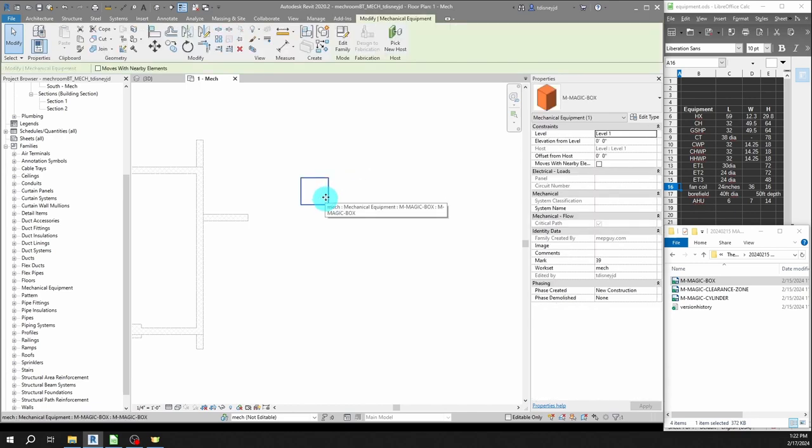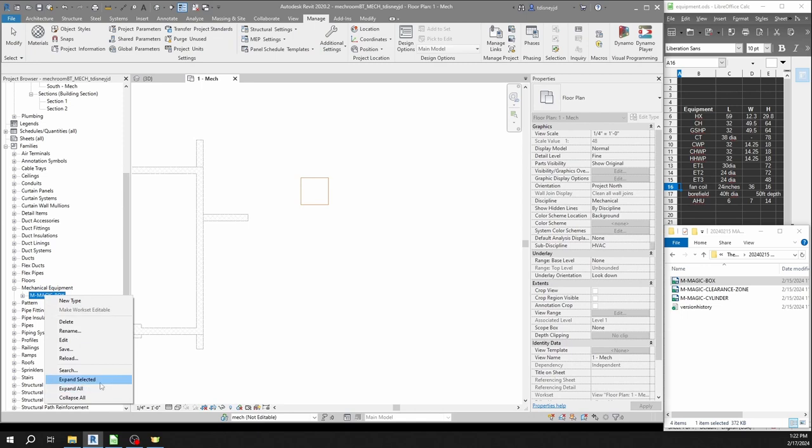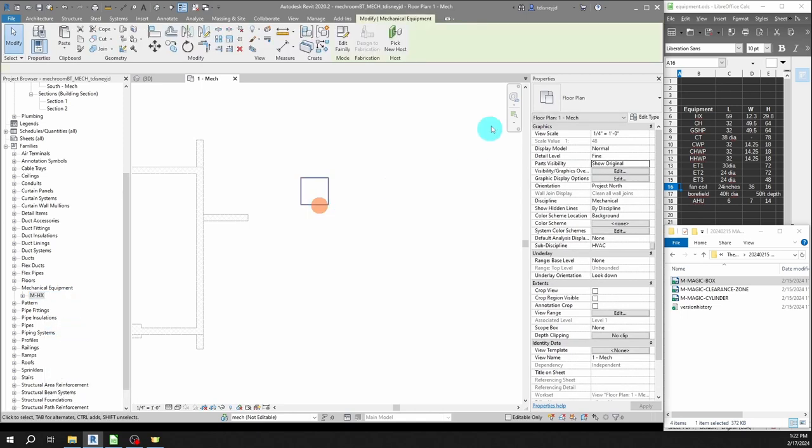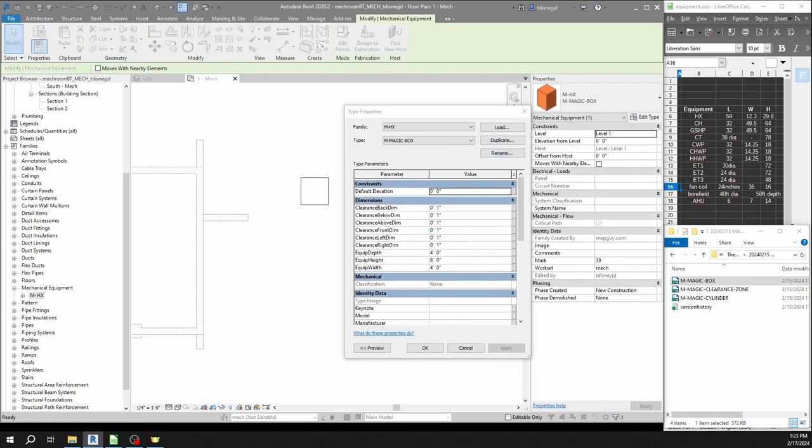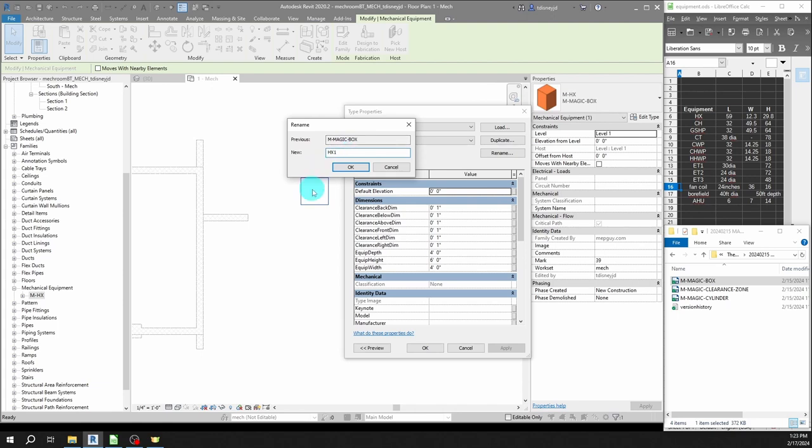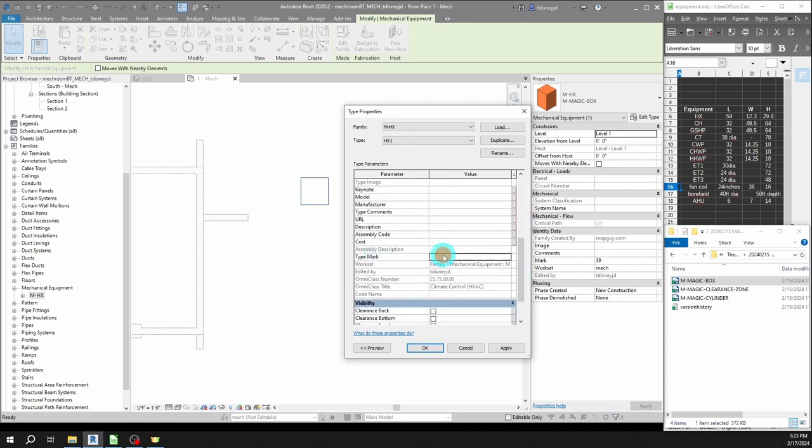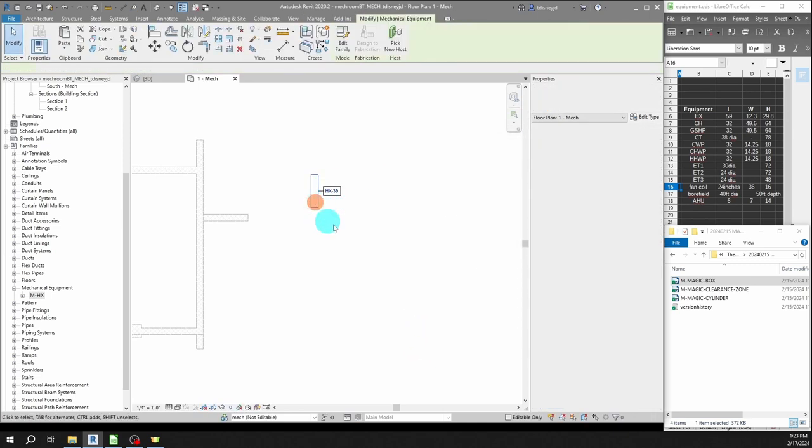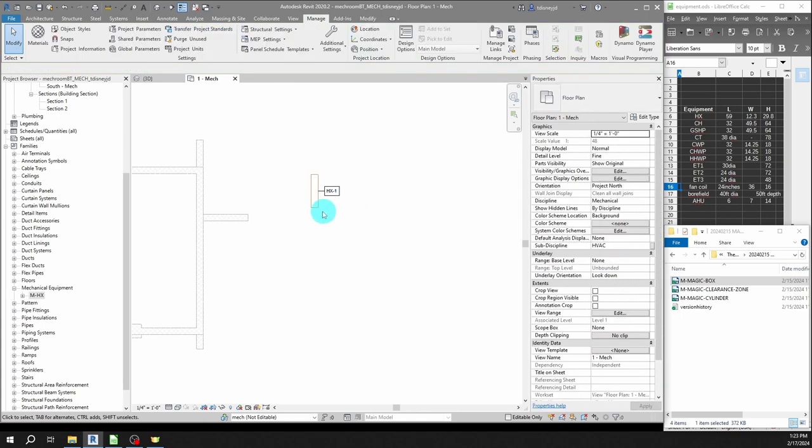We have the magic box. I want to make my heat exchanger equipment, so I've made a table of all the equipment and the rough dimensions that I need. I'm going to rename it HX dash exchanger and select this instance, edit type, rename it to exchanger one, and then set the dimensions. That's 59 inches by 29.8 inches, width is 12.3 inches. For the tag, I want my type mark to be exchanger. I'm going to tag that and set the mark to what I want it to be.